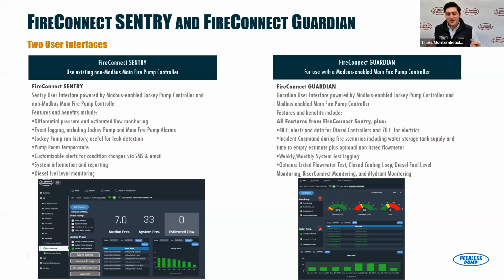Guardian means you've got a Modbus enabled main fire pump controller, so you're getting all that extra data. You're getting the 40 plus diesel data points, and the 70 plus for electrics. The end result is a slightly different looking user interface, with more notifications for Guardian versus less on Sentry. But you're still able to log your system tests with Sentry. You're still getting jockey pump data over time, that historical number. You're getting pump room temperature notifications and customizable alerts, and even diesel fuel level monitoring you can pick up with Sentry. But Guardian really takes it a step further. When you get that system trouble alarm, you're really able to dive into what's driving it.